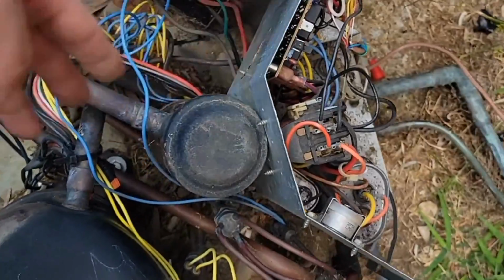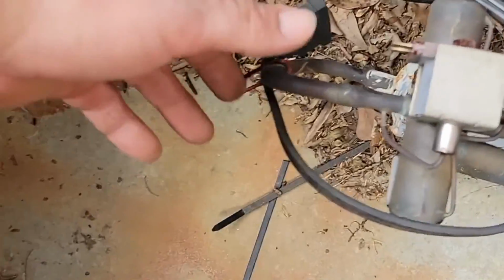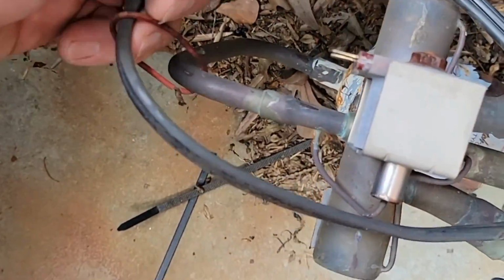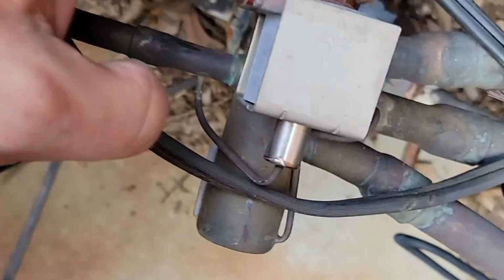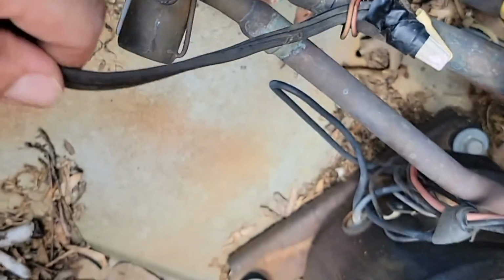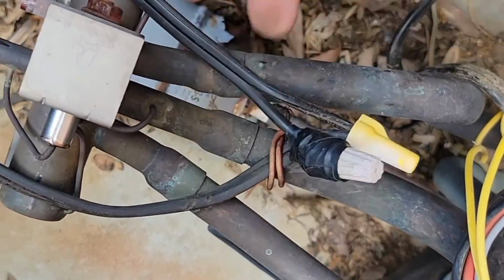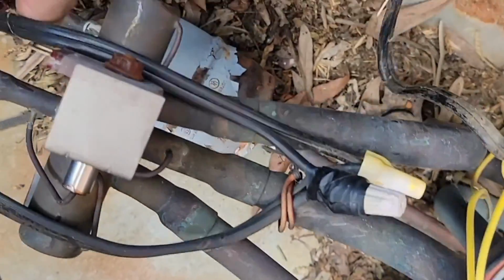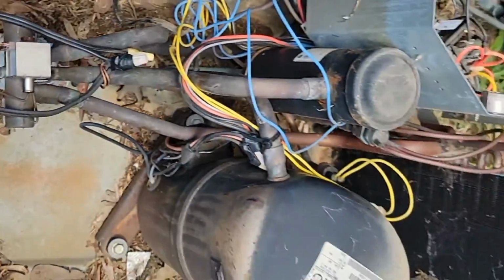All right, now we should be able to turn the breaker on, and we should not have a blown fuse. All right, so I'll just get a new coil for this reversing valve. Oh, by the way, check all the wires that go to the reversing valve coil. I checked all of them. There's nothing rubbing, nothing touching.